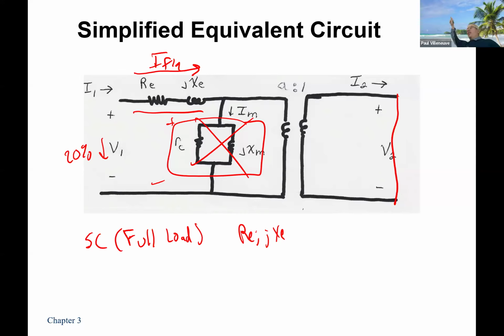All right. So how do you do a full load test? You set a dead short circuit on the secondary side. You have a variable AC power supply that you turn up until you're measuring rated current flowing into the winding. And it could be either on the primary side or the secondary side because they're going to be proportional to each other based on the turns ratio. And then you measure a bunch of parameters. What would you measure to be able to obtain RE and JXE? So I'm putting a voltage here, and it's variable. What would you need to measure to be able to calculate RE and JXE?